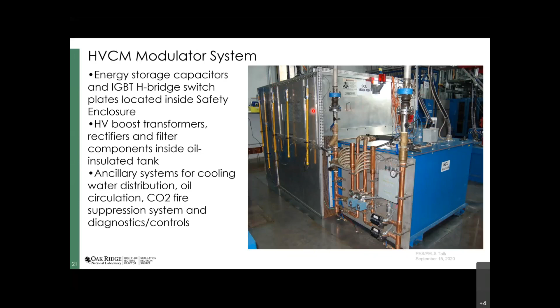This blue tank sticking out in the front is where all the high voltage components are located. The power that feeds the primary out of those H bridges feeds down through the tank into the oil submerged components. There's also a water distribution panel for cooling, an oil pump for circulation, a CO2 system in the back for fire suppression, and a variety of diagnostics and controls.